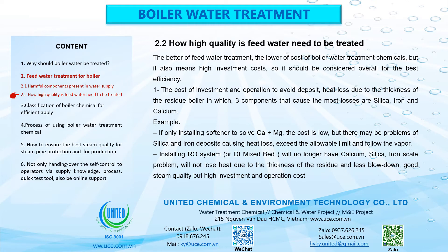2.2 How high quality does feed water need to be treated? The better the feed water treatment, the lower the cost of boiler water treatment chemicals, but it also means higher investment costs, so it should be considered overall for the best efficiency. 1. The cost of investment and operation to avoid deposit heat loss depends on the thickness of the residue in the boiler; the three components causing the most losses are silica, iron, and calcium. For example, if only a softener is installed to solve Ca plus Mg, the cost is low, but there may be problems with silica and iron deposits causing heat loss exceeding the allowable limit and following the vapor. Installing an RO system or DI mixed bed will eliminate calcium, silica, and iron scale problems, will not lose heat due to residue thickness, and will mean less blowdown and good steam quality, but at high investment and operation cost.